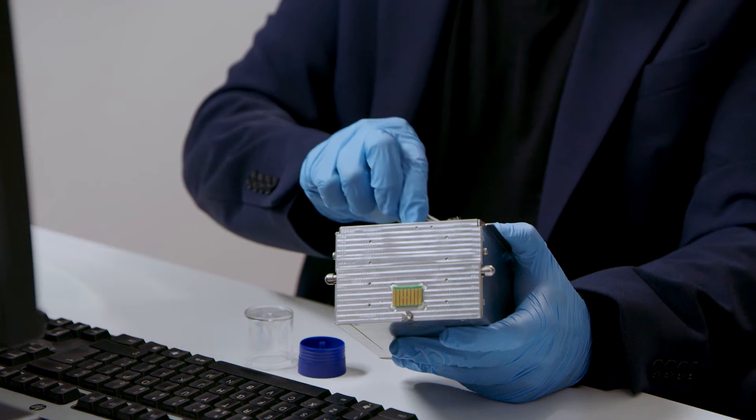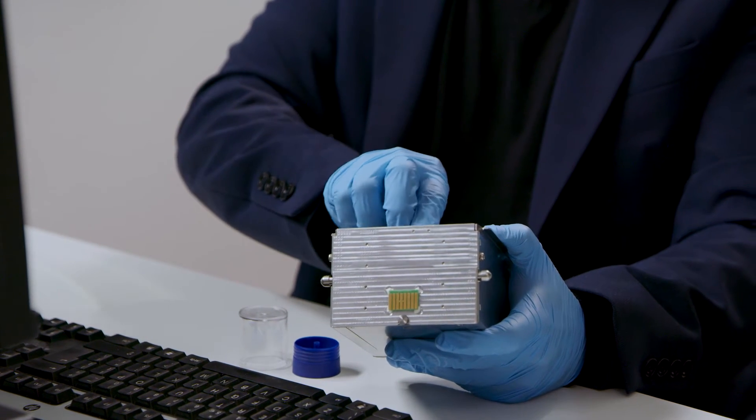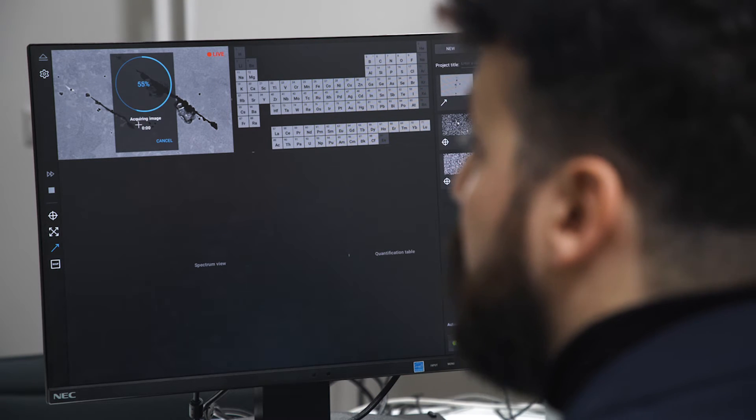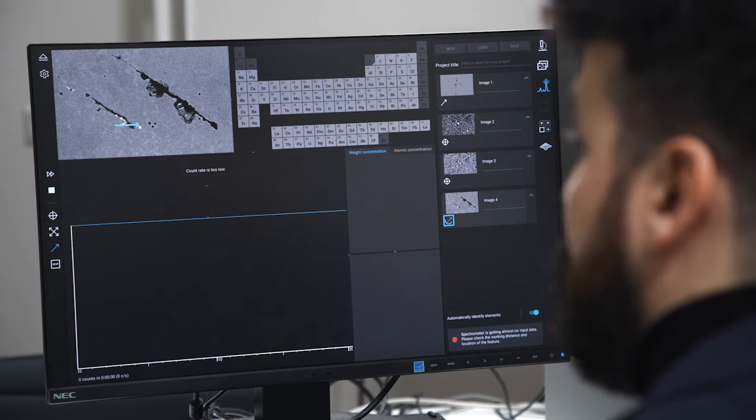As the signal is acquired by the detector, the software takes care of creating a spectrum, which is a distribution of the X-rays based on their energy content. If I now start a line scan analysis across the sample, I instruct the microscope to perform a series of analyses one after the other that creates a line and allows us to study the distribution profile of chemical composition of different elements inside our sample.